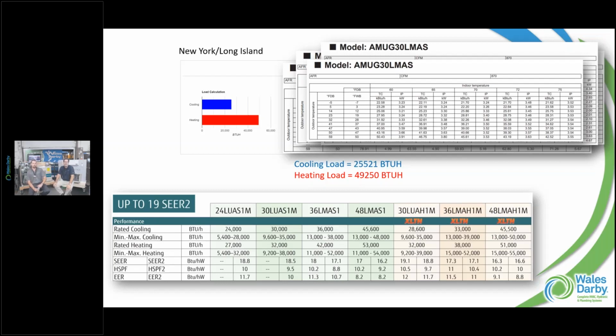What economy mode does is knock off 30% of our total capacity. So when you're dealing with short cycling and not getting the humidity control you need, if you drop that 4-ton system into economy mode, you now operate at no more than 70% of the system. On most summer days, you'll be able to run as a smaller system and get the humidity control you need. It's hard to know beforehand exactly how it'll perform, but it's an option to consider.